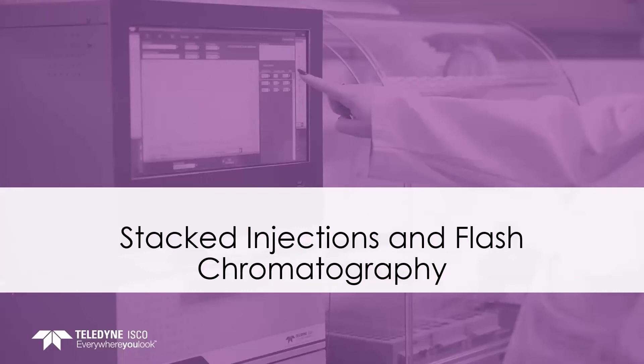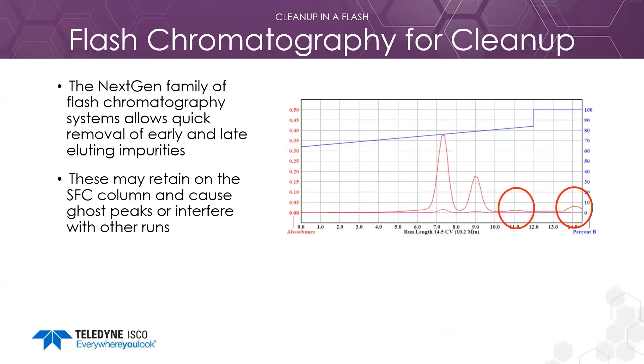Flash chromatography is a quick way to prepare samples for stacked injections. Flash is fast — it removes compounds that might interfere with isocratic SFC runs, compounds that may retain on the SFC column and elute later as ghost peaks or interfere with other runs. Flash chromatography is done very quickly in only a few minutes. Although I used a focused gradient to purify these compounds, it's possible to do the cleanup with just a standard gradient on the flash system without optimization.